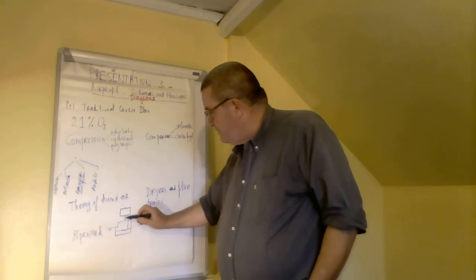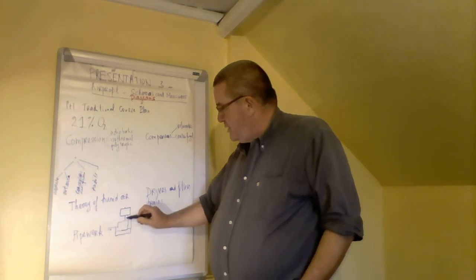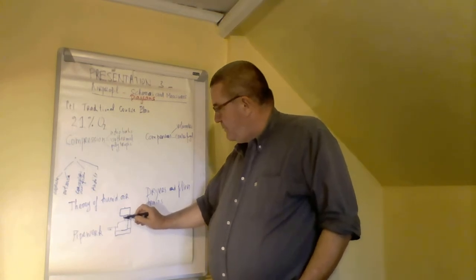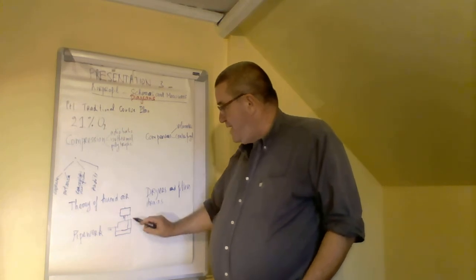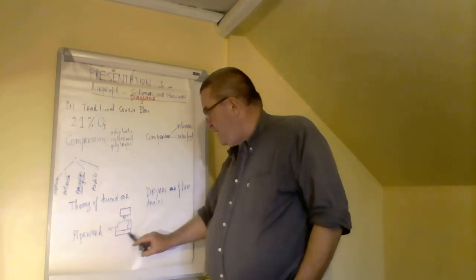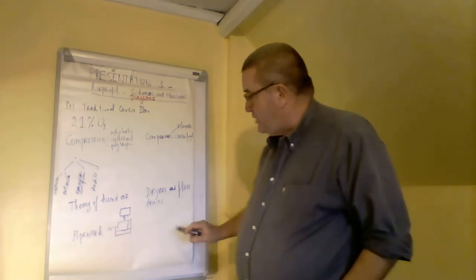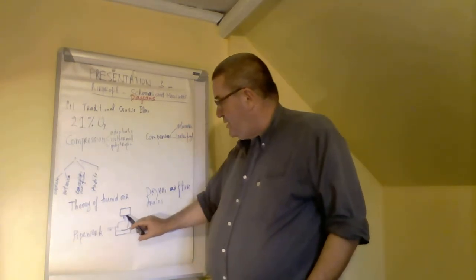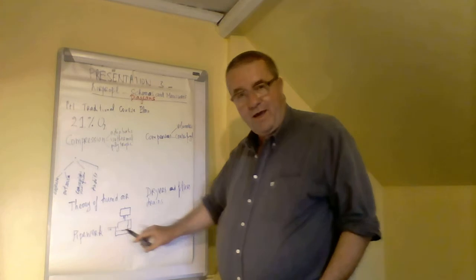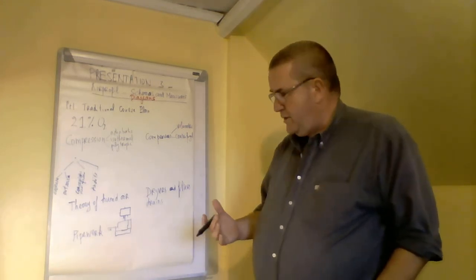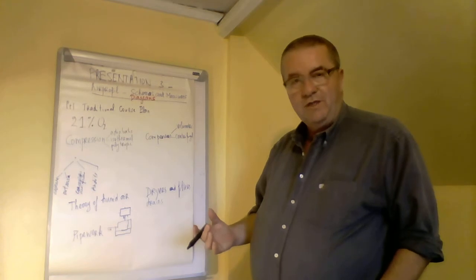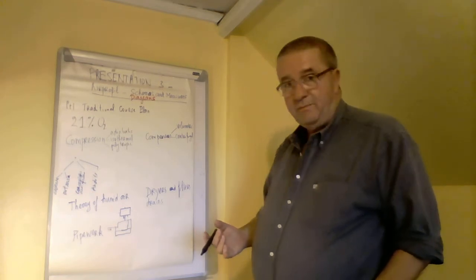For example, here you see that you may measure by putting a flow meter here. You may measure the consumption of this area, but then, to know the consumption of this other area, you would need to subtract this flow from this flow, and subtracting flows makes uncertainty of measurements very, very high sometimes.